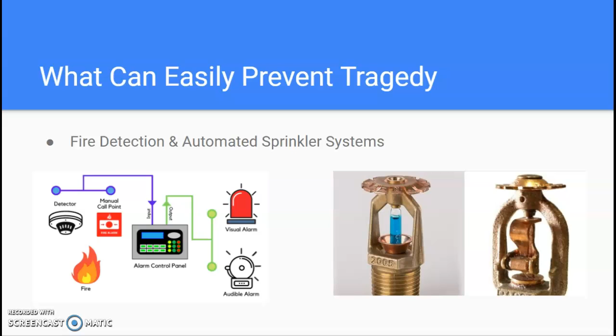Most sprinkler systems are controlled by thermally sensitive devices. Sprinklers with a fusible link, as seen on the right, have a solder link with a specific melting point. When a fire raises environmental temperatures to that melting point, the link melts and the lever arms and struts are released, allowing water to flow freely. Sprinklers with a frangible bulb, as seen on the left, have a liquid encased in a glass bulb that prevents water flow. When a fire raises environmental temperatures, this liquid expands in the bulb until it shatters, also allowing water to flow freely.